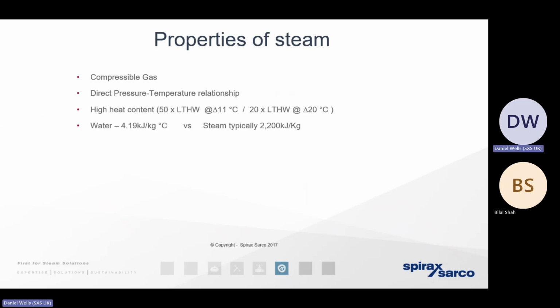Steam's got a very, very high energy density compared to water. Because steam gives up its heat energy by condensing, and because water gives up its heat energy by cooling down, it means that we can get the energy from the steam into the process very, very quickly. It also tells us that we've got approximately 50 times more energy present within a kilogram of steam compared to a kilogram of water when that water's circulated across a heat exchanger, for example. So, of course, with the steam system, if we're comparing a steam boiler to a hot water boiler, the steam boiler is significantly smaller in space and it can generate a greater mass of energy more rapidly.